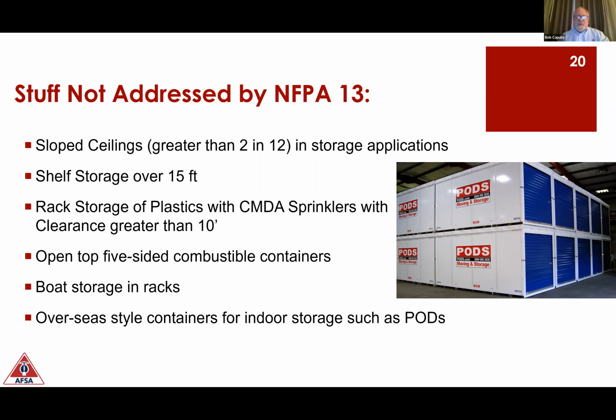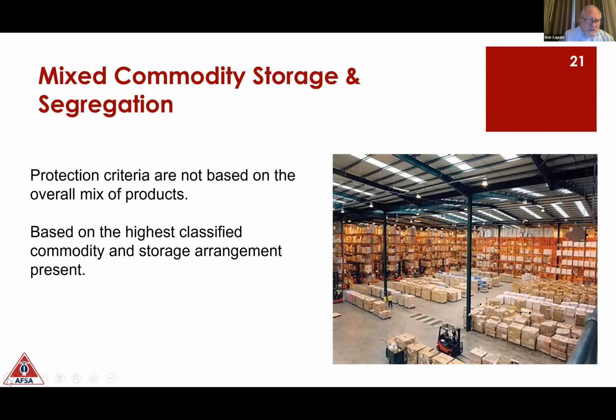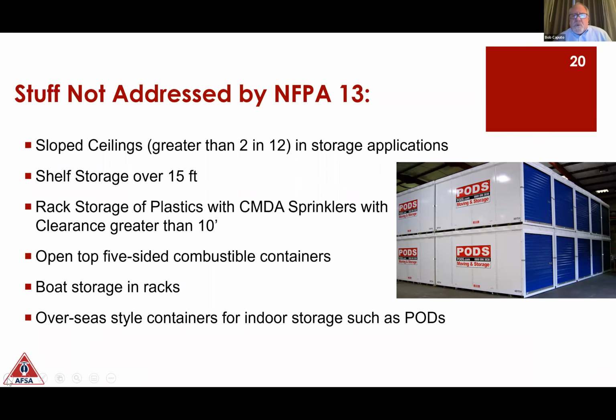Now, there are things that are not addressed by NFPA 13. First of all, you can't have storage in a building where the ceiling slope is greater than 2 in 12 or 16.7%. So you can't have a storage application in a Quonset hut. You can't have shelf storage over 15 feet, which is probably not something you care about. But whoops, most importantly, and I got to go back to that slide, sorry. There are some things we don't give you criteria for in the standard, including these pods, right? So all the combustibles are hidden in these containers, and the heat is not going to get to the sprinklers, and the water is not going to penetrate this metal box to go attack the fire. Things like boat storage on racks, but these overseas containers indoors, these are the kind of things that make life tough.